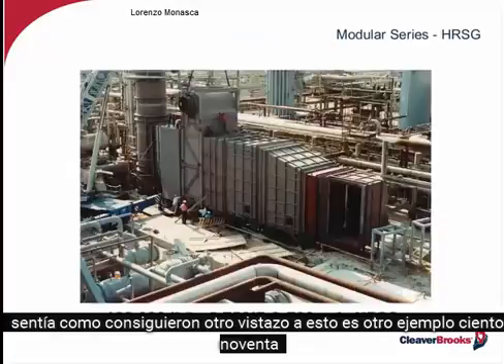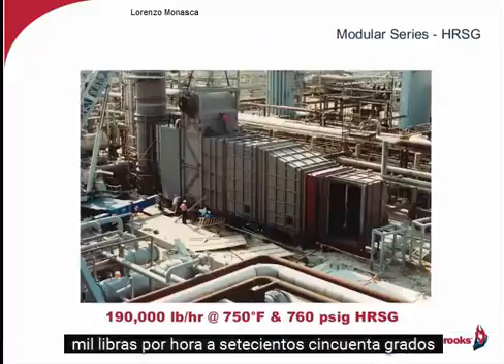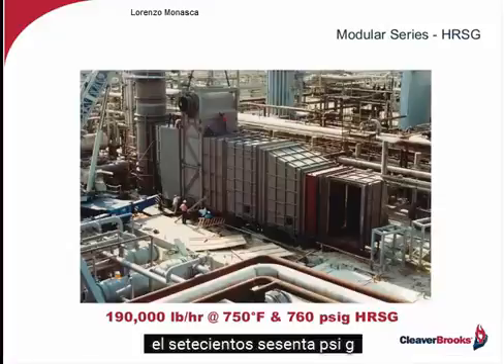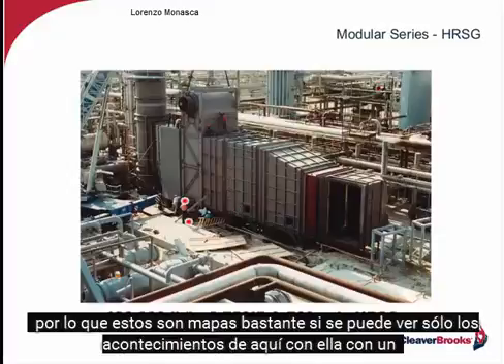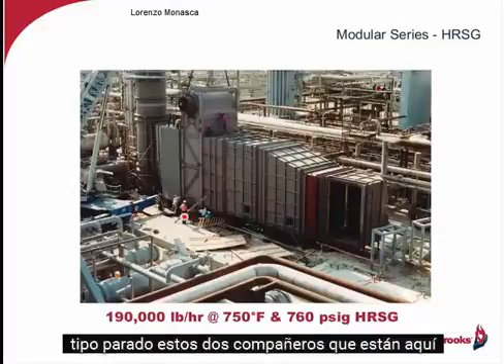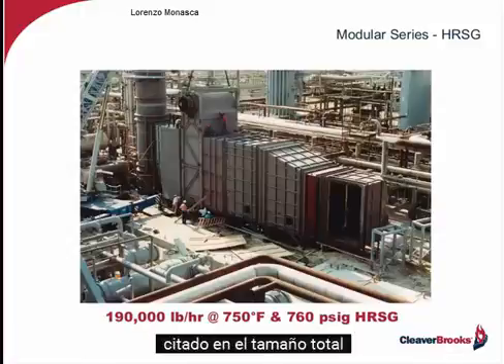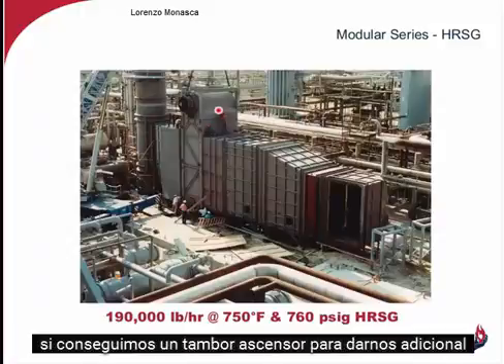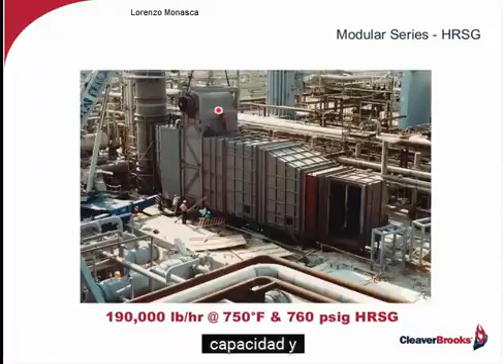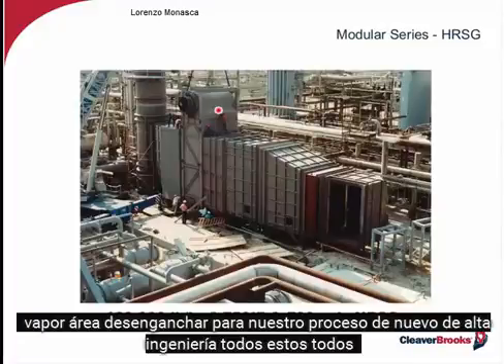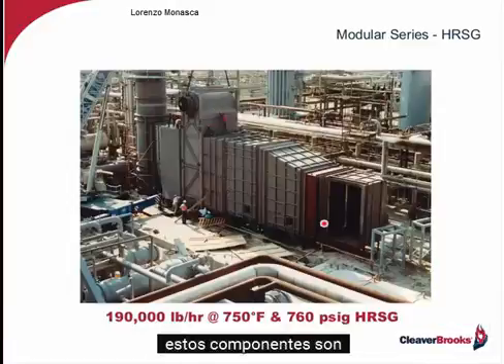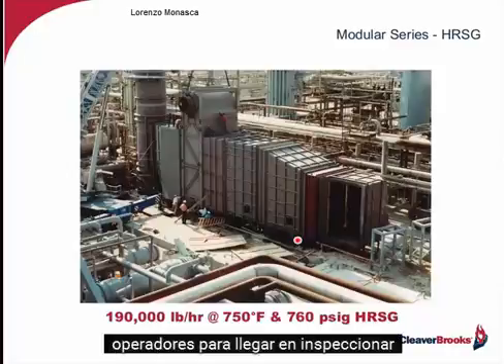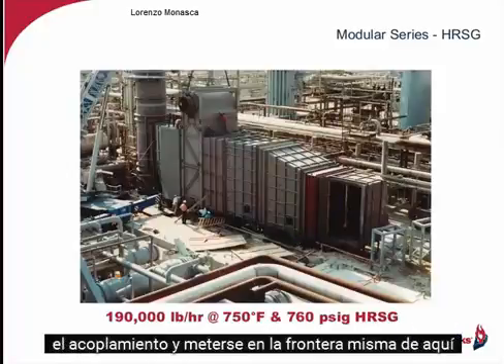Now, here's another example, 190,000 pounds per hour at 750 degrees and 760 psig operating. So these are quite massive. You can see the relative size with these two fellows standing here. This has an elevated drum to give us additional capacity and steam disengaging area for our process. Again, highly engineered, all these components are. Note the access ways here as well, to allow the operators to get in and inspect the ducting and get into the boiler itself from here.